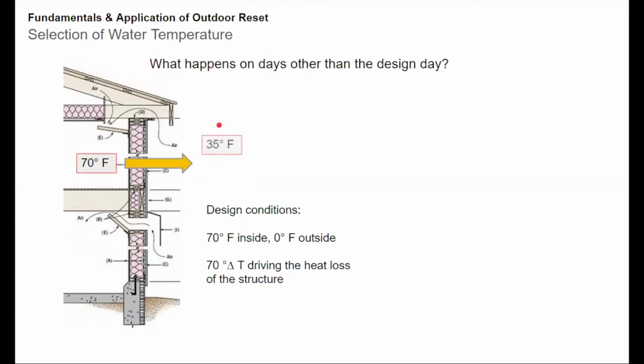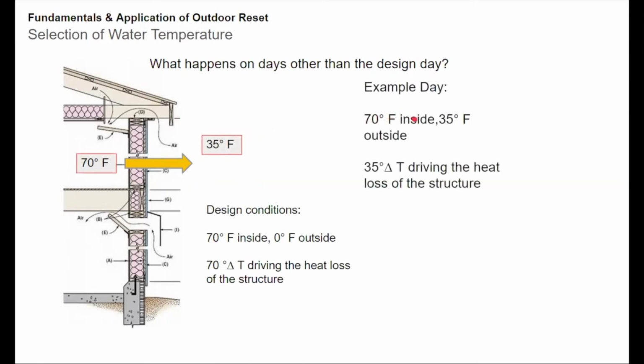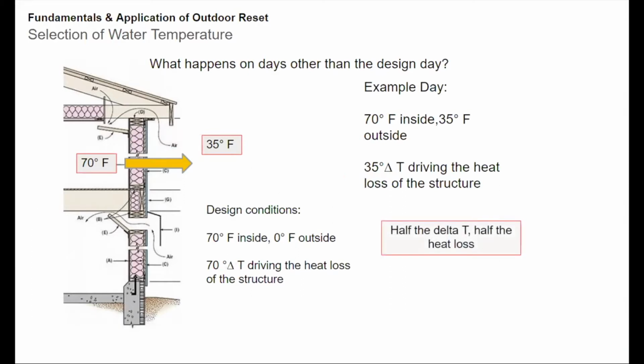Some days, the temperature is only 35 degrees. So on a 35-degree day, I'm now 70 degrees on the inside and 35 degrees on the outside. That represents only about a 35-degree delta T driving heat through the building's structure, versus the 70-degree delta T that I've designed for. So if I have half the delta T, I only have half of the heat loss. So all of a sudden, this building that was designed for design conditions, if I don't do anything to balance the rest of the process, I'm putting twice as much energy into the building space than is needed to heat that building.